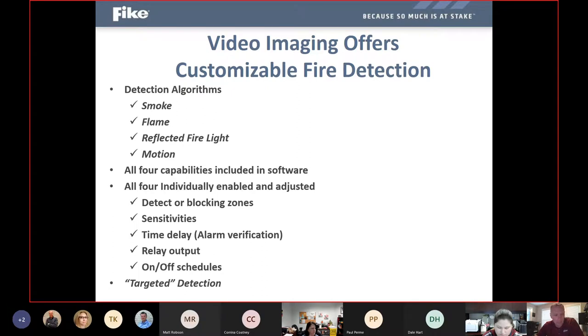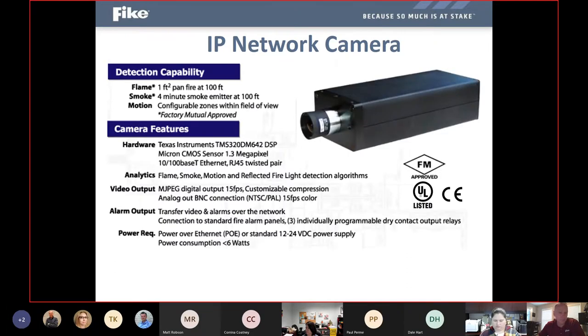And what the video imaging detection allows many folks to do is to achieve very targeted detection in areas that otherwise might be very difficult to address, especially when you have very large open areas like warehouses or hangars or any vestibule with very high ceilings. Trying to detect something that's happening on the floor all the way up at the ceiling introduces a lot of other elements of delay and performance that we can rule out by using video imaging detection, because anything in that camera's field of view is fair game that we can look to program to detect.